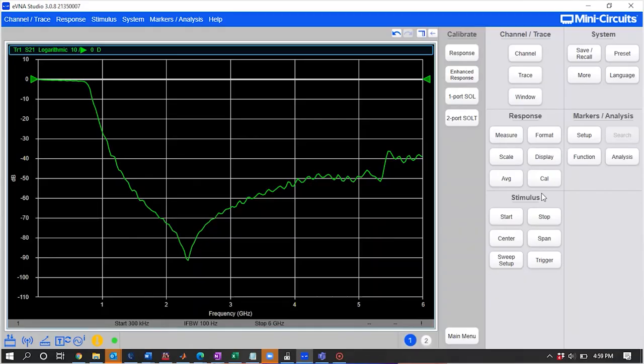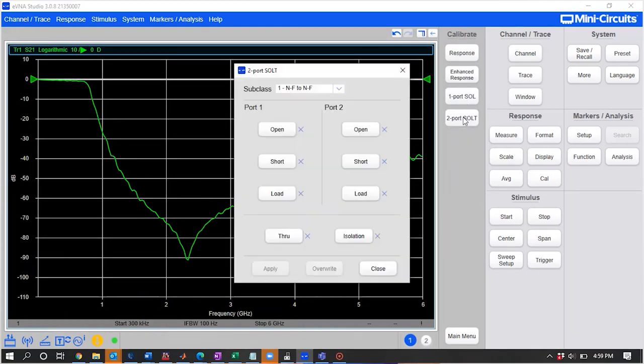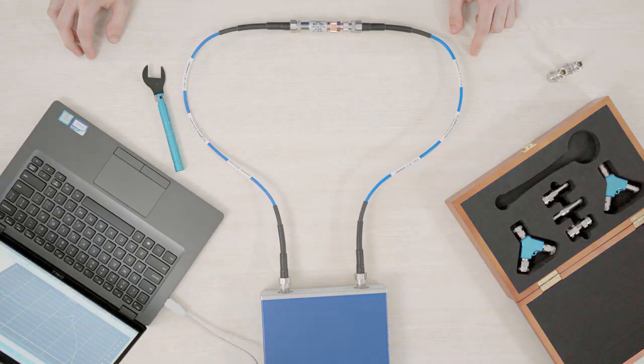Next, you want to set the calibration type. Here, I'm selecting full two-port SOLT method. Now you should see a pop-up menu with the standards you need to measure. At the top, choose the device subclass. The device subclass defines the connector types of the DUT. Our DUT has an N-male connector on port 1 and an N-female connector on port 2, so this is an N-male to N-female subclass device.